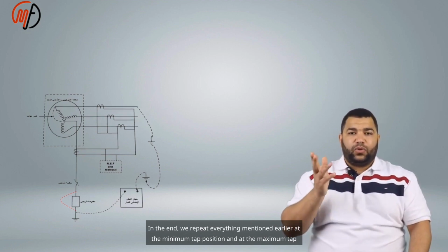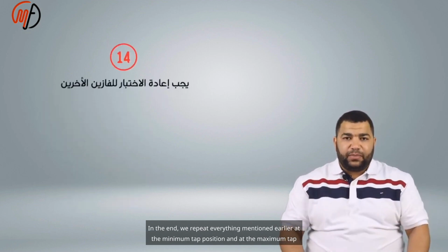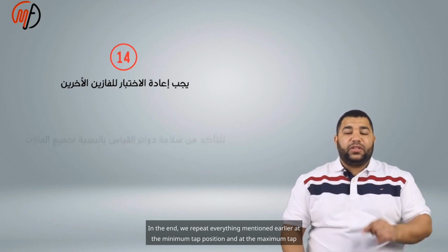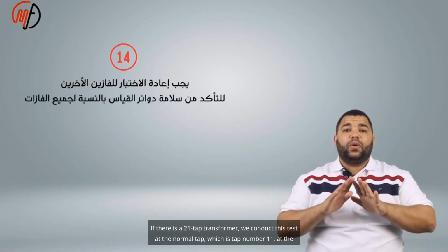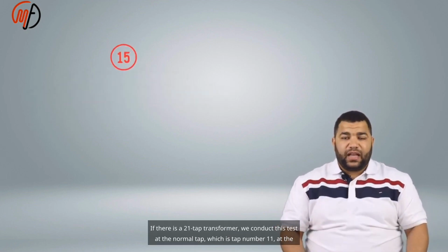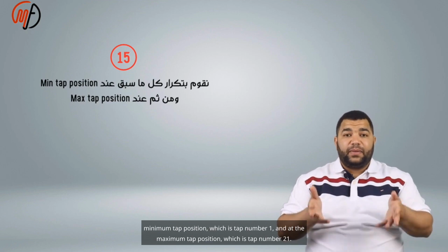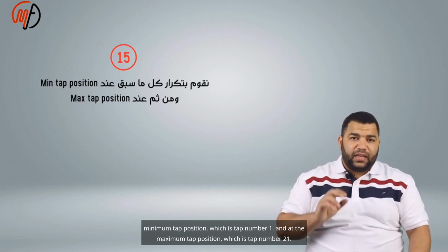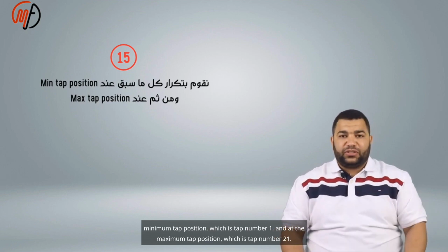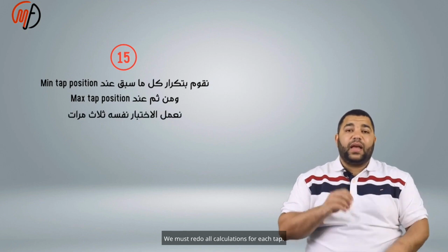In the end, we repeat everything mentioned earlier at the minimum tap position and at the maximum tap position. If there is a 21 tap transformer, we conduct this test at the normal tap, which is tap number 11, at the minimum tap position, which is tap number 1, and at the maximum tap position, which is tap number 21. We must redo all calculations for each tap.